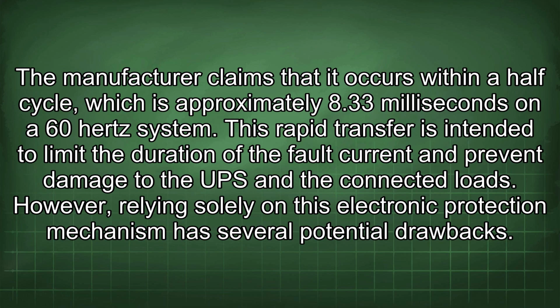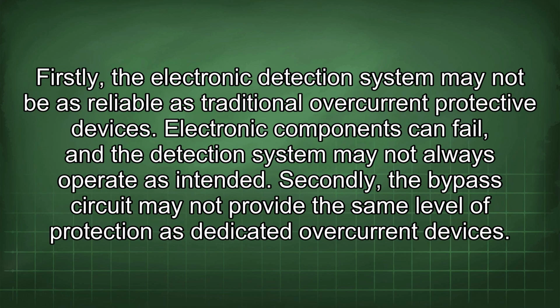This rapid transfer is intended to limit the duration of the fault current and prevent damage to the UPS and the connected loads. However, relying solely on this electronic protection mechanism has several potential drawbacks. Firstly, the electronic detection system may not be as reliable as traditional overcurrent protective devices. Electronic components can fail, and the detection system may not always operate as intended. Secondly, the bypass circuit may not provide the same level of protection as dedicated overcurrent devices.